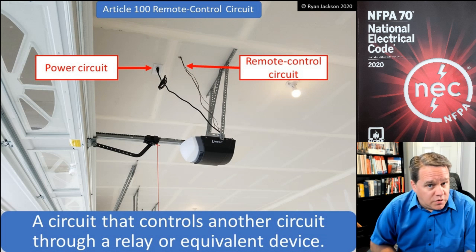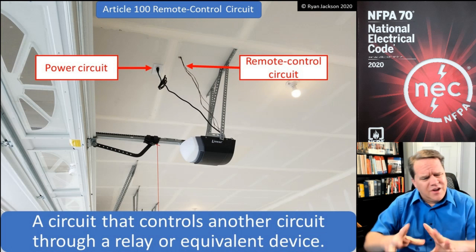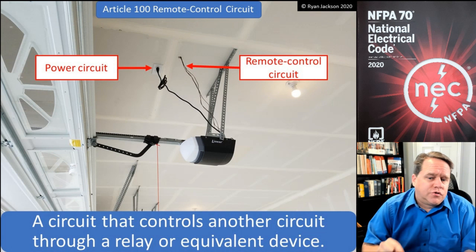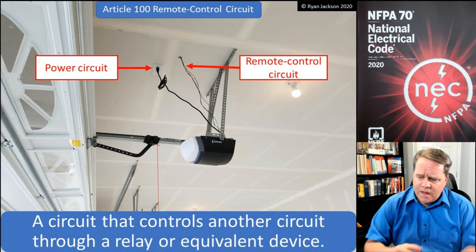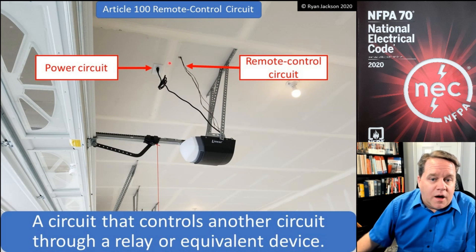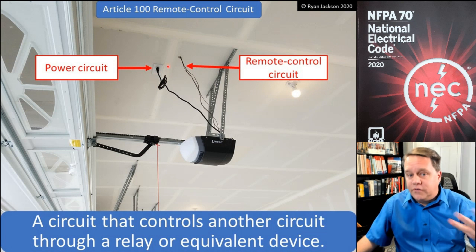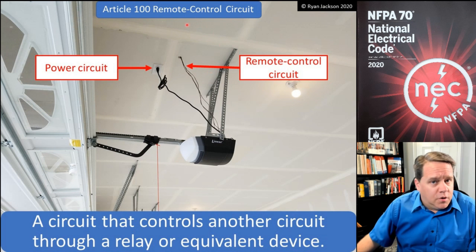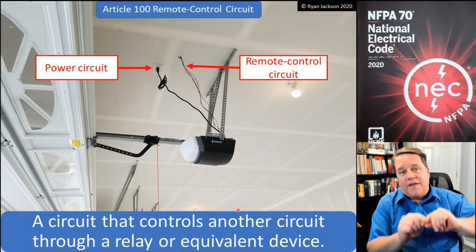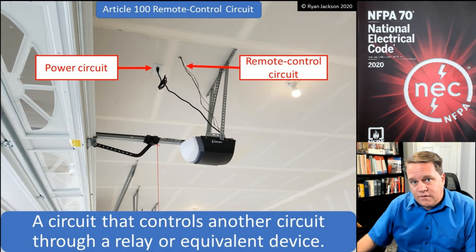The next definition is a remote control circuit. A remote control circuit is a circuit that controls another circuit through a relay or equivalent device. The best, most relatable example is the garage door opener. You have the power circuit — that's chapters 1 through 4 of the NEC, using MC cable, boxes, wire connectors — and then the remote control circuit goes from the opener itself over to the push button on the wall. Those low-voltage wires control the power circuit through a relay.